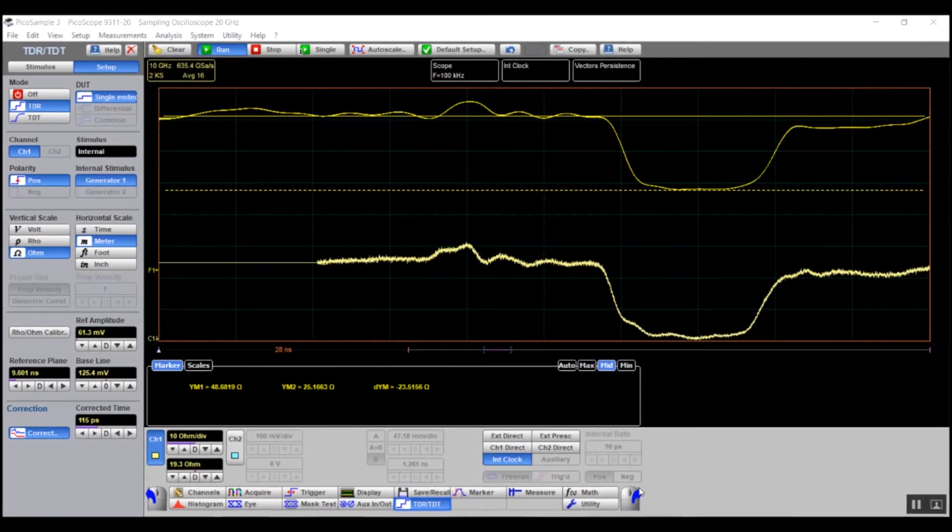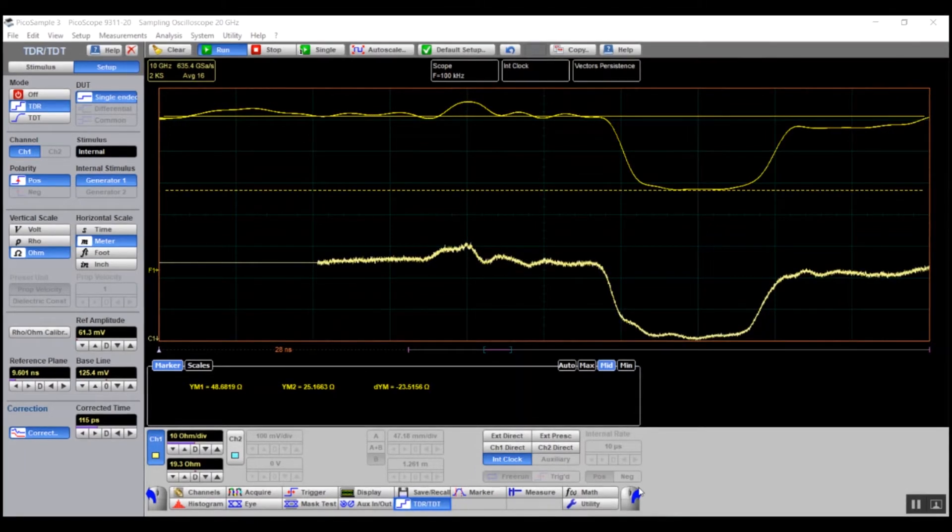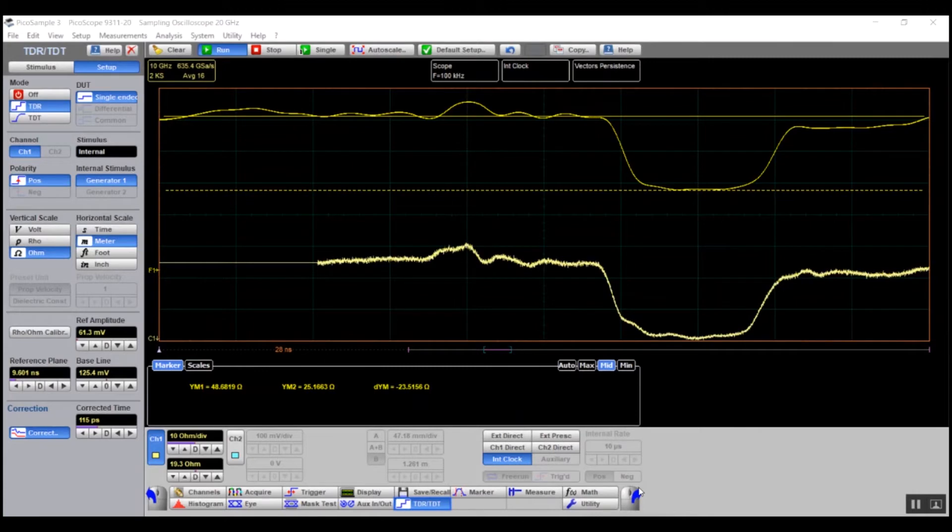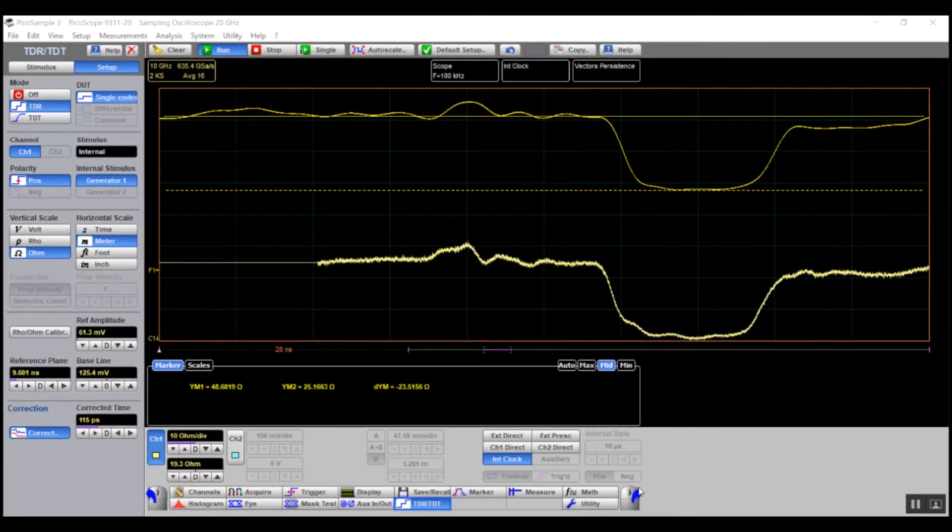The setup menu allows you to make TDR and TDT measurements for any configuration: single-ended, differential or common. You can select any channel and any stimulus to configure your TDR system.